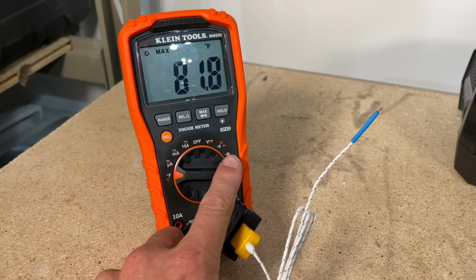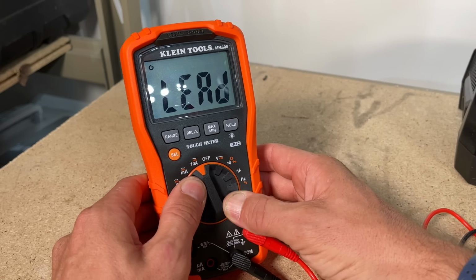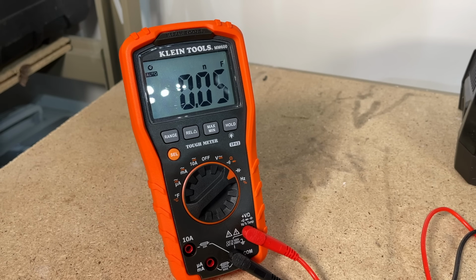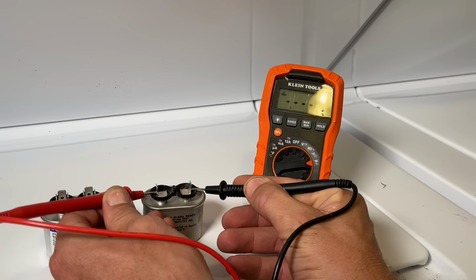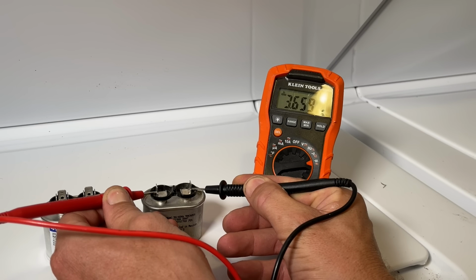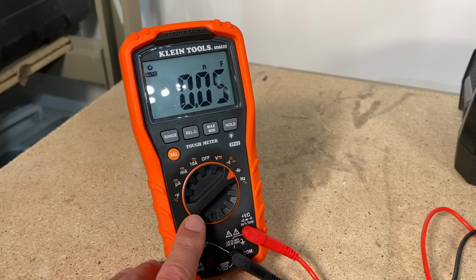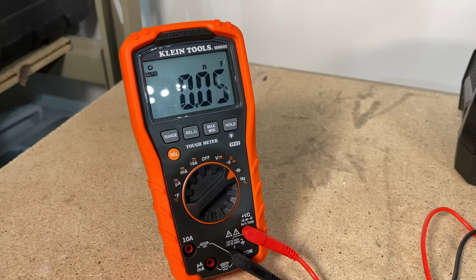On to the last one: capacitance. Similar to temperature, this is pretty short since I really only use it to measure capacitors. Within my HVAC system, I had a failure on the blower motor where my 5 microfarad capacitor wasn't reading within the tolerance range. I identified that with my multimeter and knew exactly which component to replace, which saved me hundreds of dollars compared to bringing out a technician. I ordered it online, got it in less than 2 days, installed it, and solved the problem. So capacitors can come in handy, usually found in your HVAC system but also in other systems you might run into.